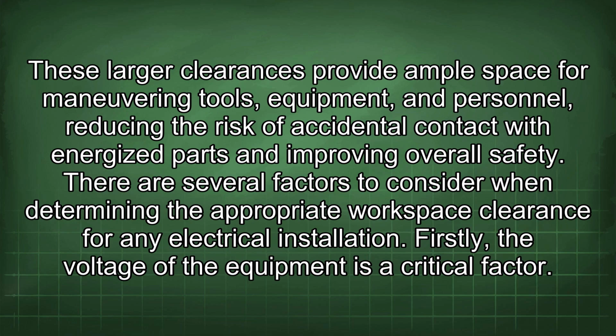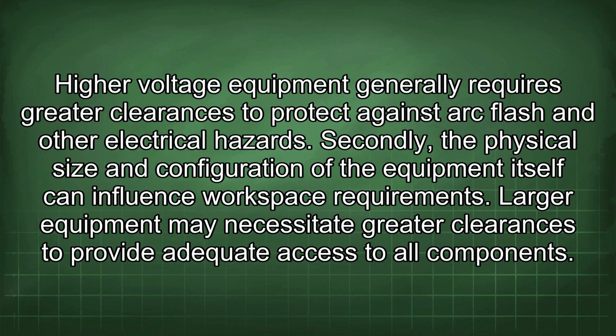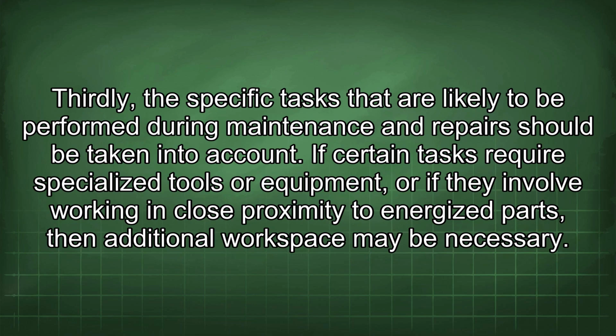There are several factors to consider when determining the appropriate workspace clearance for any electrical installation. Firstly, the voltage of the equipment is a critical factor. Higher voltage equipment generally requires greater clearances to protect against arc flash and other electrical hazards. Secondly, the physical size and configuration of the equipment itself can influence workspace requirements. Larger equipment may necessitate greater clearances to provide adequate access to all components. Thirdly, the specific tasks that are likely to be performed during maintenance and repairs should be taken into account. If certain tasks require specialized tools or equipment, or if they involve working in close proximity to energized parts, then additional workspace may be necessary.